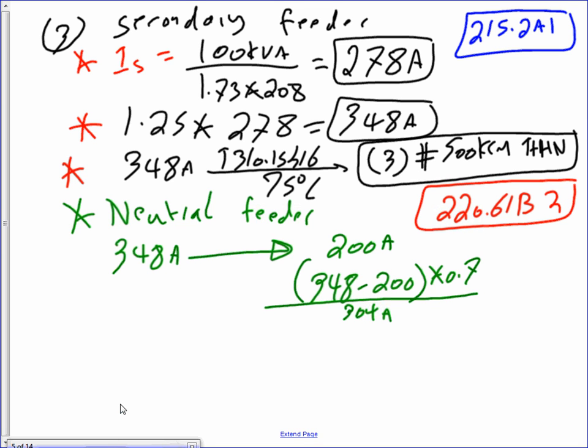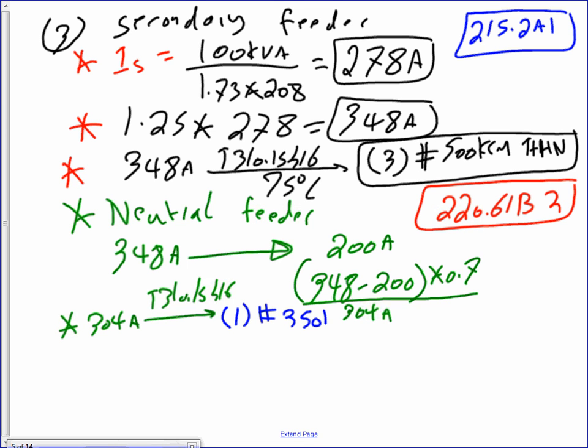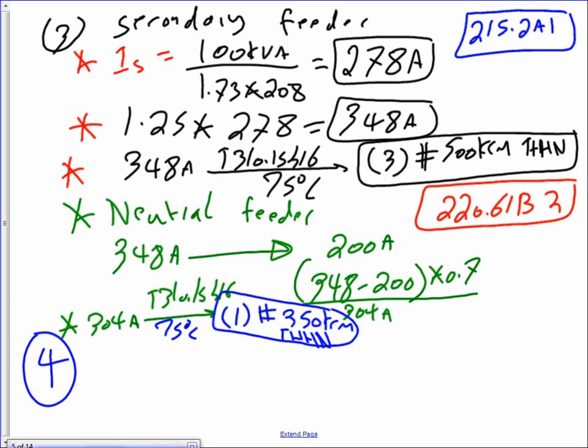Then take the 304 amps, take it to the same table, table 310.15(B)(16), and that will get you a healthy conductor. One conductor, what size did we come up with? One conductor, 350 kcmil THHN, 75 degree. Any comments, guys? Any questions? So that's how I size my neutral.